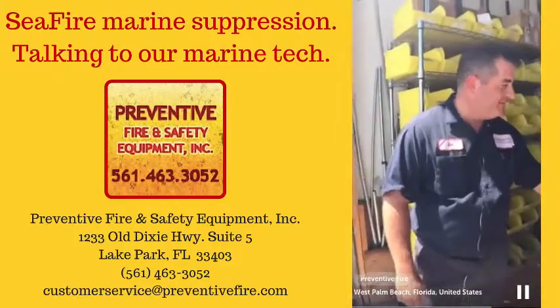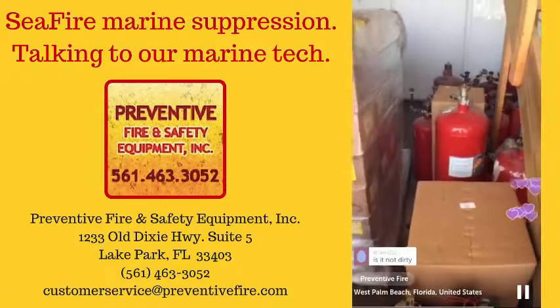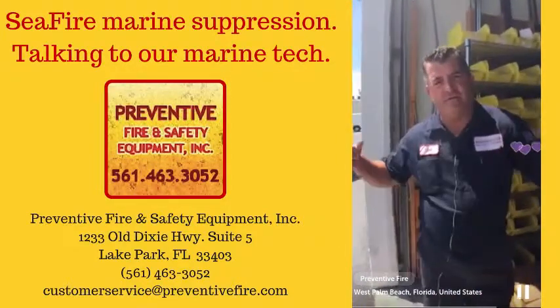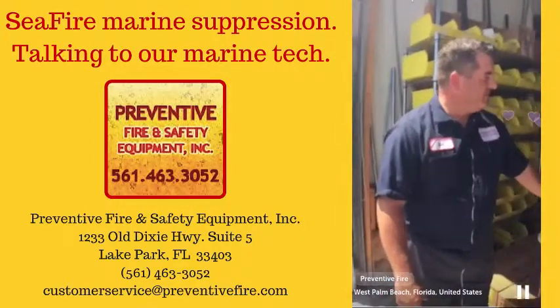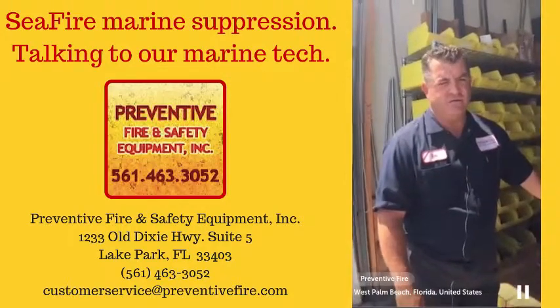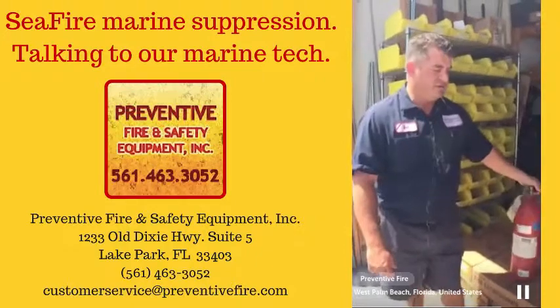Clean agent. For example, in one of these cylinders back here, those are kitchen system cylinders. They are a dry chemical cylinder, meaning that when that goes off, it's like taking a bucket of baby powder and throwing it all over everything. Bottom line, that's what it is. The chemicals are just not made to be in a space like an engine room. The older boats, ones from Europe I've seen, do have dry chemical, and we remove them. Clean agent, on the other hand, does not damage any of the components, electrical, engines.